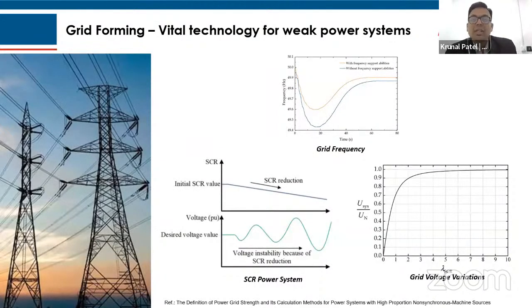Now, if we look at any power system, there are three parameters. The first is grid frequency. In any big power system, when a fault happens, the frequency will fluctuate, and the grid forming inverter should adjust that frequency to a certain band and limit it. Second, the short circuit ratio.